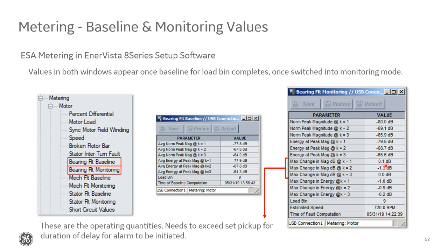So these max change values are the actual operating quantities. These values are what need to exceed the set pickup for the ESA function to alarm. Ideally, you want to see values like this that are close to zero, which means that there's been no deterioration seen in the motor. Again, we show you what load bin we're currently operating in. In the monitoring values, we also show you the speed, the time that the baseline was recorded, and the time of the last fault computation.